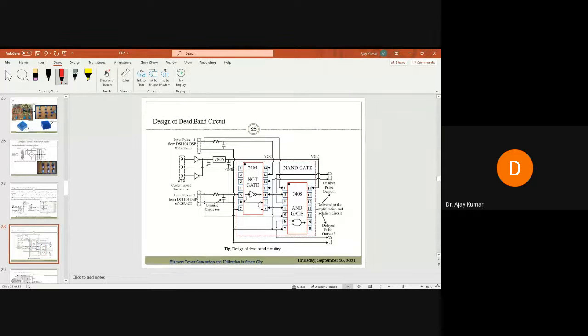If you are not able to generate the minimum required dead band, the complete leg of the inverter will be short circuited. To avoid that, you need extra deadband circuitry of 2, 3, or 5 microseconds. This gap is between the incoming pulse for switch 1 and the outgoing pulse, with the second switch off. Once the first switch goes off, there must be a gap, and only after that gap should the second switch turn on. This gap between incoming and outgoing pulses is designed using the deadband circuitry.